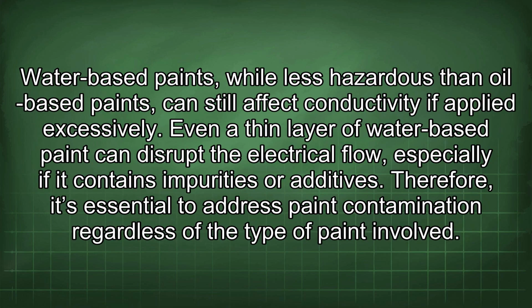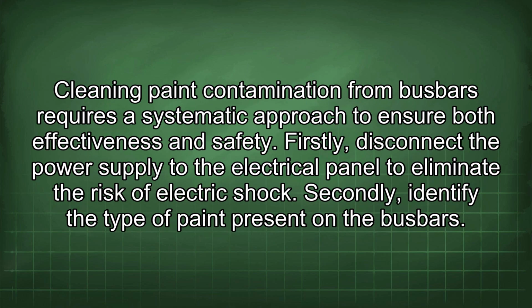Water-based paints, while less hazardous than oil-based paints, can still affect conductivity if applied excessively. Even a thin layer of water-based paint can disrupt the electrical flow, especially if it contains impurities or additives. Therefore, it's essential to address paint contamination regardless of the type of paint involved. Cleaning paint contamination from busbars requires a systematic approach to ensure both effectiveness and safety.